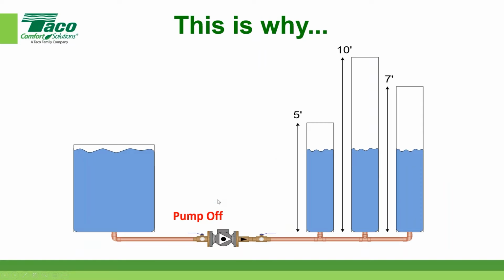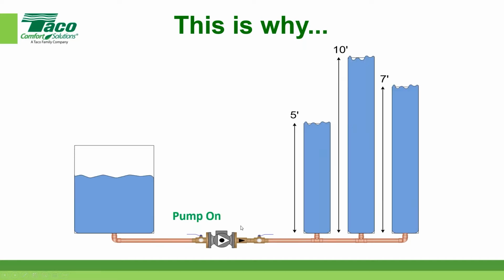If I had a pump here, it's in the off position, I'm pumping out, it's an open system. I'm using this just to explain. Same thing applies to closed loop. If I had atmospheric pressure on this, I'll see the liquid level here. You could see I'm level. If I turn the circulator on, then I'm going to pull this down and I'm going to push these up. As you can see, these columns full of water are being pushed up.